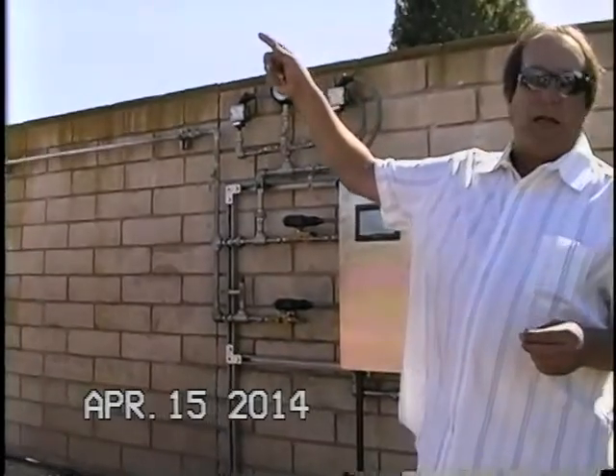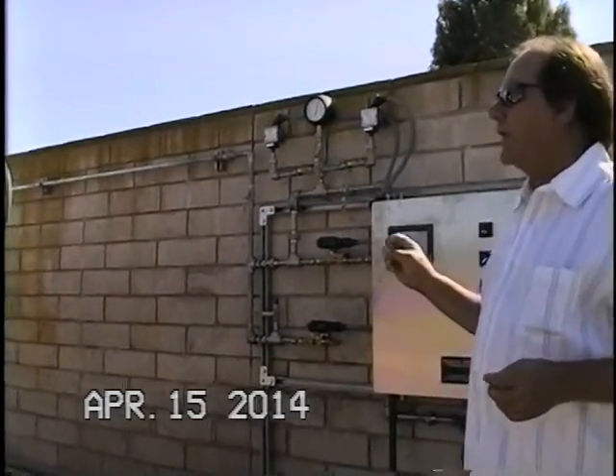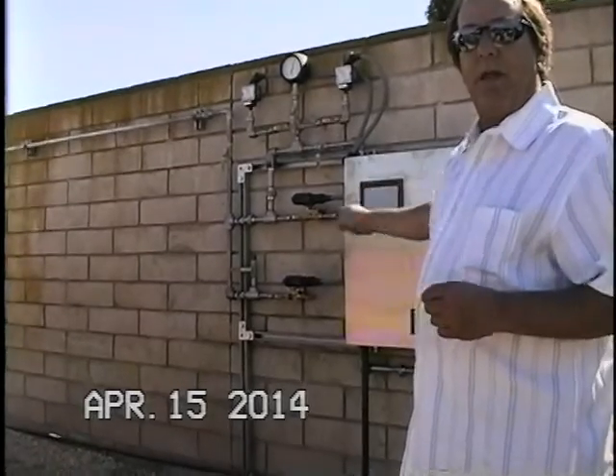One of the things that I'd like to mention is that if you find that this RF probe, and the nice thing is we're going to set their liquid levels with the gauge, and they'll be marked. And one of the things that you can do is that those are known liquid levels. So if our steady state's at 50%, that tank is 96-inch diameter, we should be right around 48 inches, and we should be reading the same over here in our OIT. If you find that you're seeing a fairly large difference between the actual and what it's reading here, you can calibrate that RF probe.